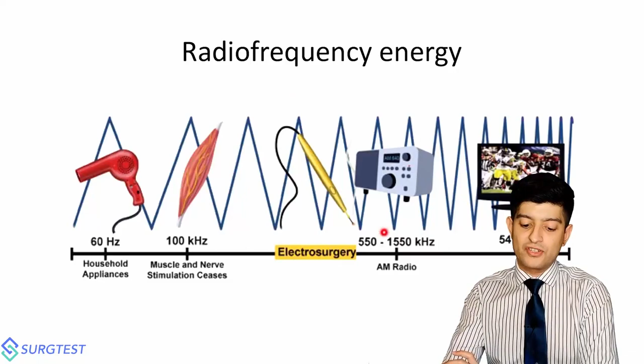The reason I'm reminding you of that is because you need to remember that the frequency of electricity within our wall sockets is 60 hertz and the voltage is 240. This device, the electrosurgical unit or the generator as we so lovingly call it, does a few very important functions. The first of which is it changes the frequency of the alternating current from 60 hertz to 5 lakh hertz. That's a massive jump.